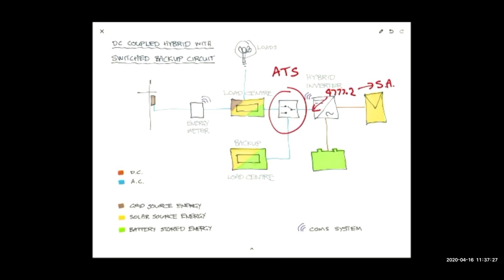So that might take some 10 seconds or so. So this type of system is characterized by when there is a failure in grid power, the lights go out, and then they come back on again, because that inverter has to switch modes from a grid paralleling system to a standalone inverter, and it has to do it in isolation from the grid. So that is one way of providing backup when the inverter actually only has one AC port.